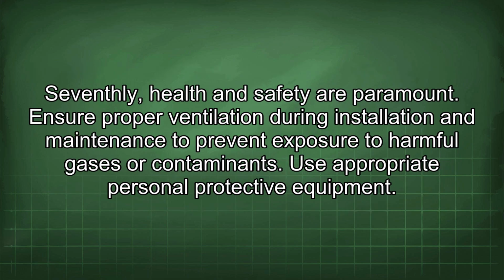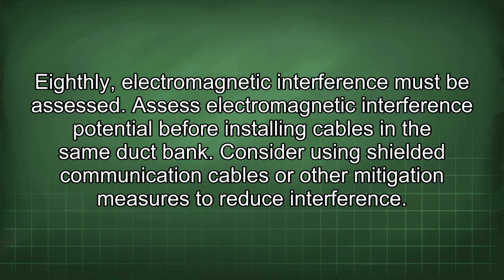Seventhly, health and safety are paramount. Ensure proper ventilation during installation and maintenance to prevent exposure to harmful gases or contaminants. Use appropriate personal protective equipment. Eighthly, electromagnetic interference must be assessed. Assess electromagnetic interference potential before installing cables in the same duct bank. Consider using shielded communication cables or other mitigation measures to reduce interference.